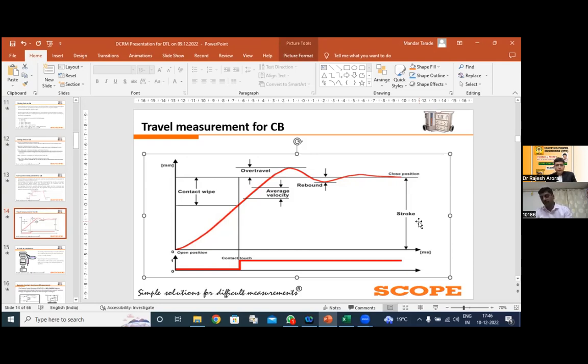The third thing is travel, which I already explained. We place the transducer resistive element on our mechanism, and according to the change in the position of the mechanism during the make and break of the circuit breaker, we get the travel test, and accordingly we do the analysis of that travel test.